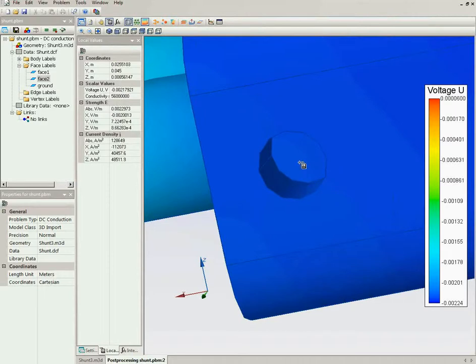The right plate has an electric potential of minus 2.17 millivolts. So for this specific shunt, the allowed current is 100 amperes and the voltage drop on the terminals will be 2.17 millivolts.